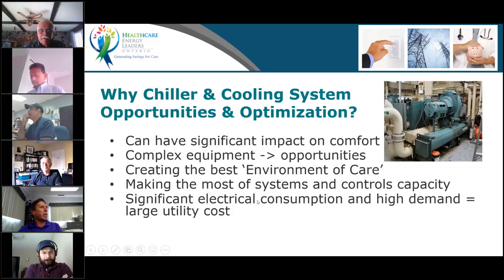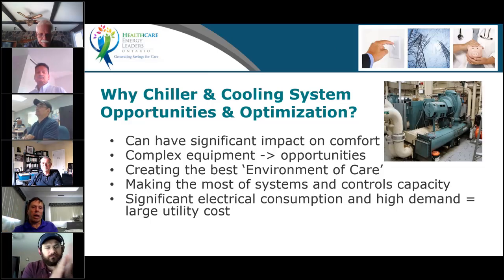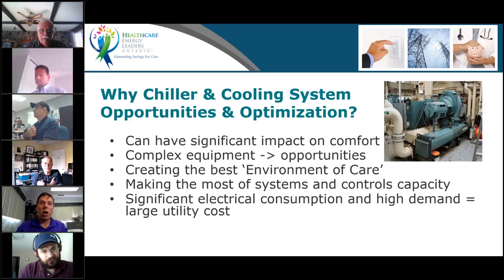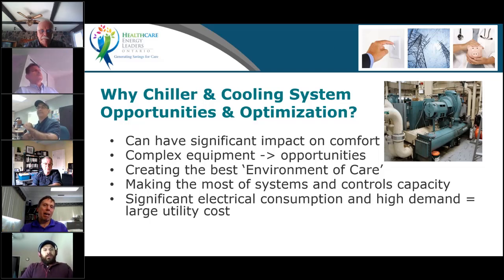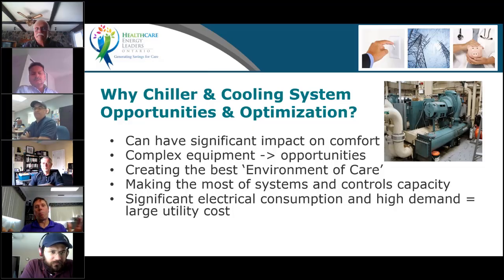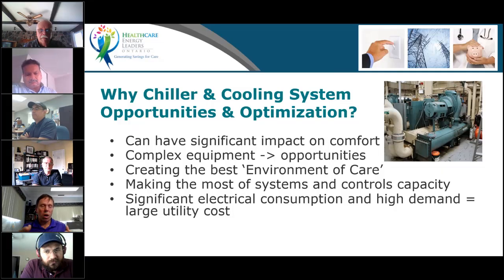So there are obviously opportunities both in terms of energy usage and better interior conditions. You can sometimes provide more capacity with the same machine, and we'll talk about Delta T, for example, that can create limited capacity on a given machine. It's also very often one of the highest demand equipment in the building. We're talking about Class A and Class B. If you're a Class A and for some reason you start your chiller, a second chiller or a third chiller at a wrong time of the day, that can really hit you bad on your GA cost. So if there's one equipment that can actually hurt you on GA, it's a chiller. It can hurt you on demand if you don't start it properly, if you really load it up and fully load for an hour or a half hour. So those are things you have to be aware of.